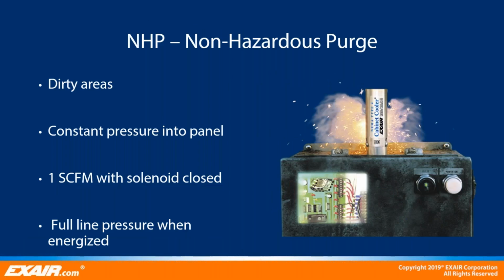Non-hazardous purge cabinet cooler systems are the preferred choice for areas with high contaminants that may pass through a conduit or small openings in the panel. The non-hazardous purge cabinet cooling systems apply a constant small amount of positive pressure into the enclosure by passing 1 SCFM of air through the cabinet cooler when the solenoid valve is in the closed position. When the thermostat detects high temperature, the solenoid valve is energized to pass full line pressure and volume to the cabinet cooler, providing the full rated cooling capacity for the system.